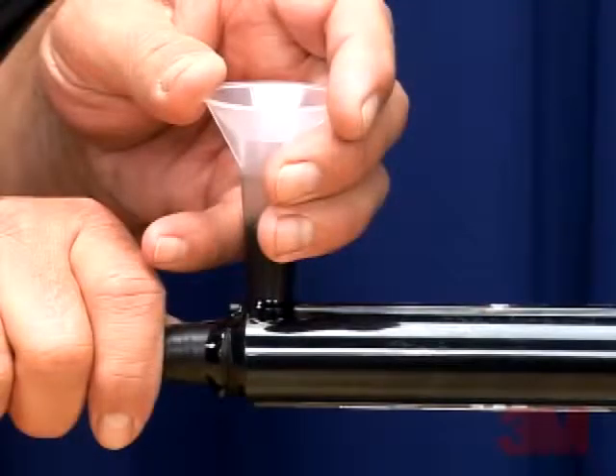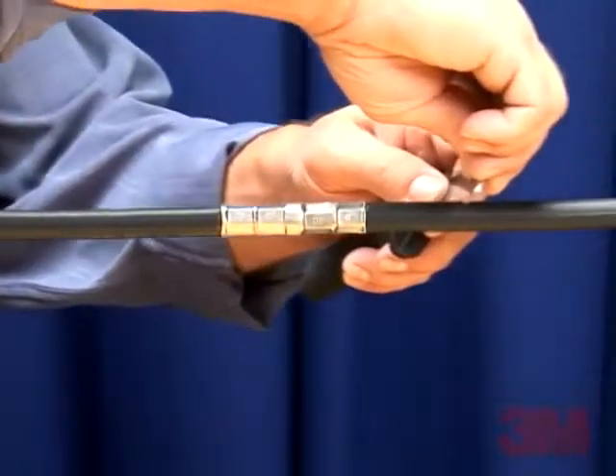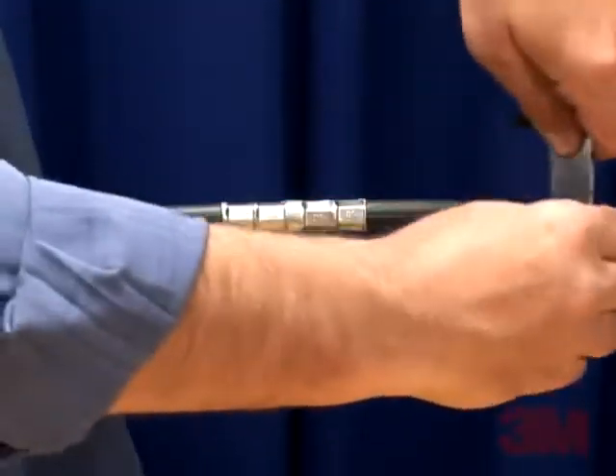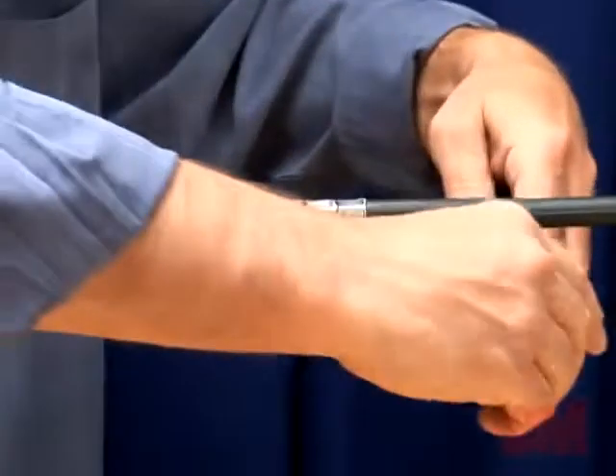In this video you'll see how to apply the 3M brand 82-A1 power cable splice kit in 4 easy to follow steps. Step 1: Prepare the cable by thoroughly scraping all wax and dirt 5 inches back from each cable end.